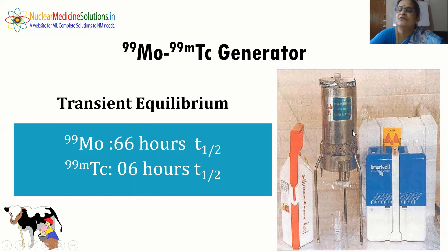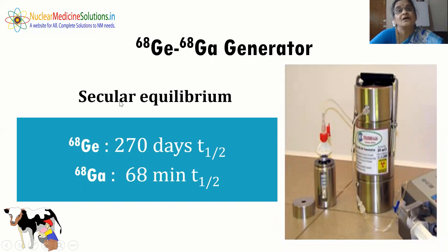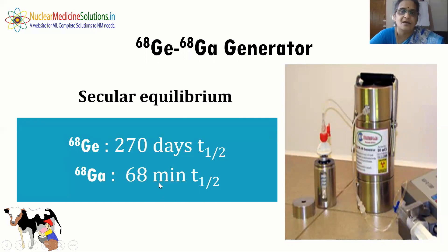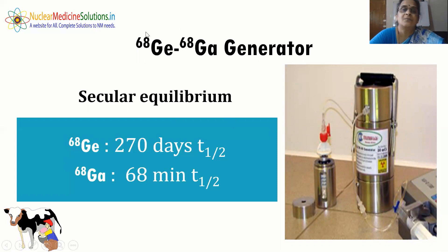The Mo-99/Tc-99m generator has evolved from manual to automated forms. The Ge-68/Ga-68 generator follows secular equilibrium due to Ge-68's very long half-life, while Ga-68 has a half-life of only 68 minutes. Ga-68 is a PET radionuclide (positron emitter) with potential to become a workhorse PET radionuclide if radiolabeling is optimized. Ge-68 can also serve as a QC source for PET imaging systems, using the positron emission from its daughter directly.